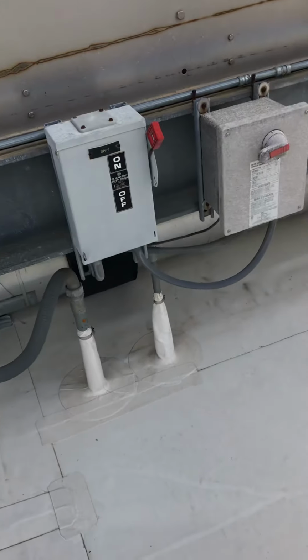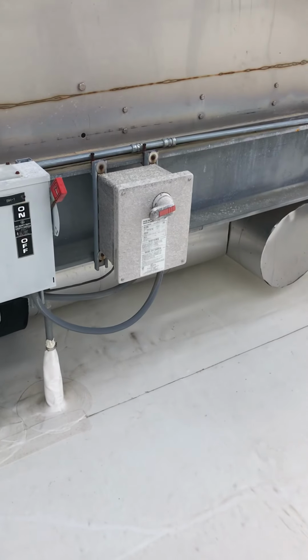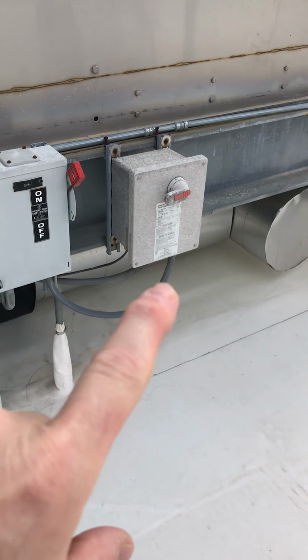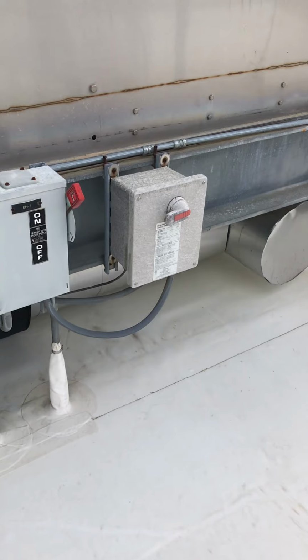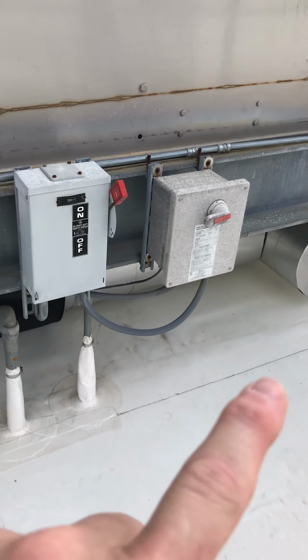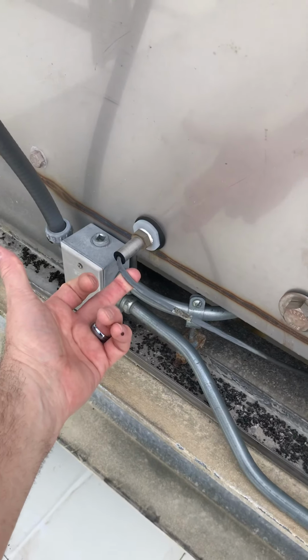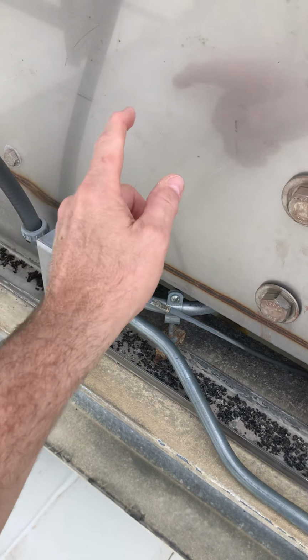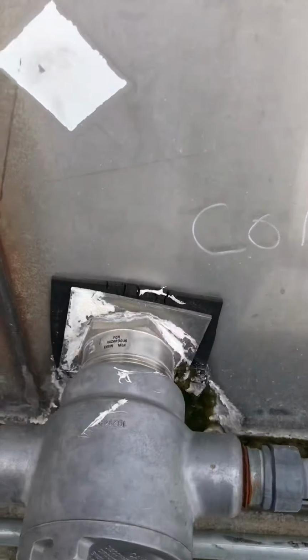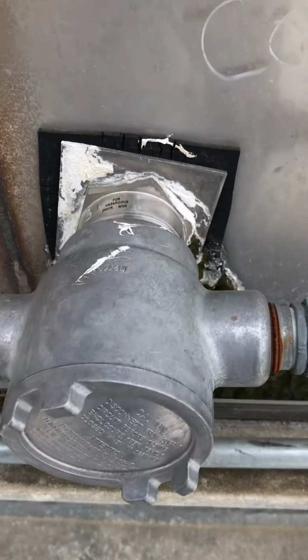So what we do is, let me see if I can get our controller. We have a controller that's set up within this box here at about 35 degrees. What it does, it brings a contactor on. It senses a water temp through this sensor right here, and when this tells us that this water is below 35, our heater comes on.